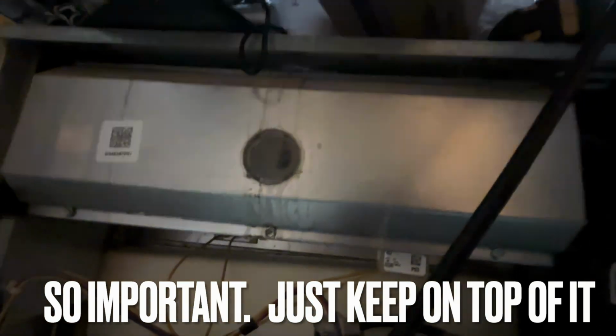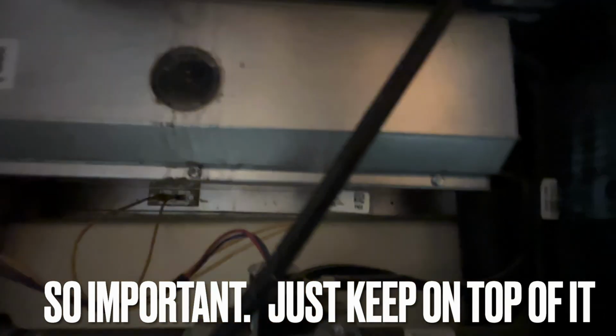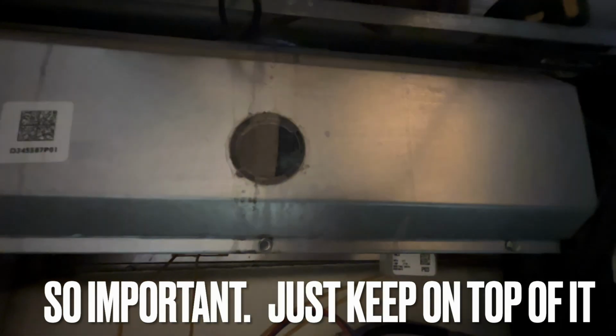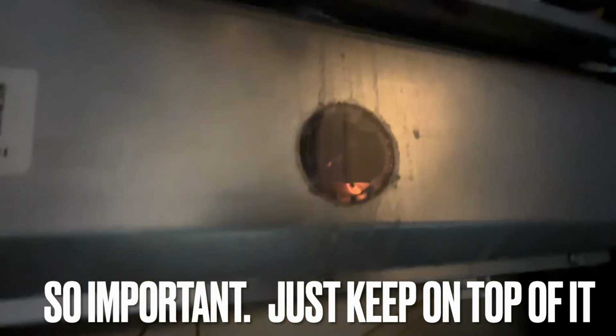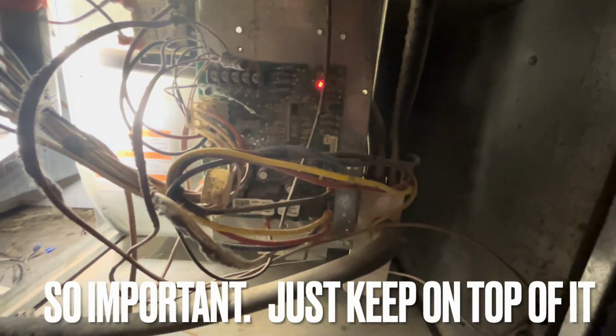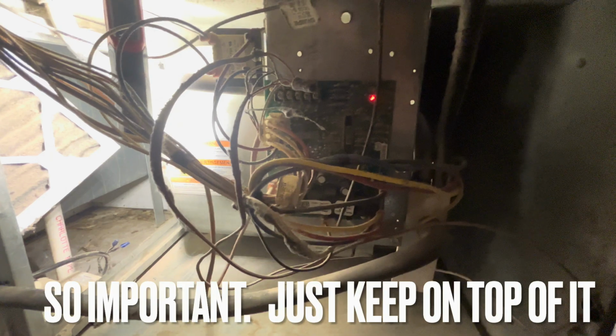Let's see what happens. So that's the inducer. Not going to bore you with the startup, but once it's started, there's your HSI. I'll bore you with it. Do the flame sensor, clean out the ports. I have a vacuum, I'll pull out this trap drain water, and let's see what happens.